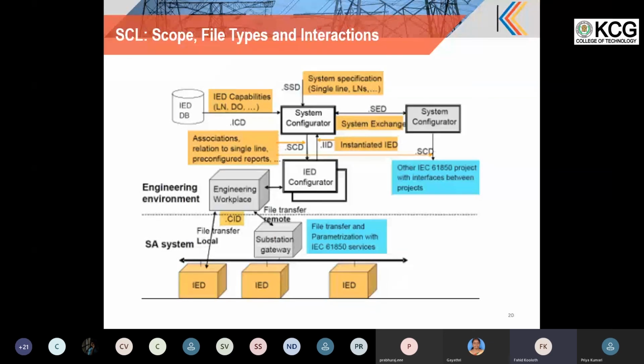This is represented by a format known as .SSD, substation specification description. Once that is done, that specifies the substation, we need to take the real data from multiple IEDs. For those IEDs, a superset is published giving their capabilities. That is known as an ICD file, the IED capability description file. For all the IED models, this is a published standard, so we can get it from the global database and use it in the system configuration. This is the real data coming from the IEDs, which is the ICD file, the IED capability description.